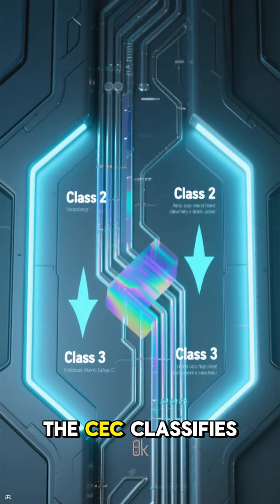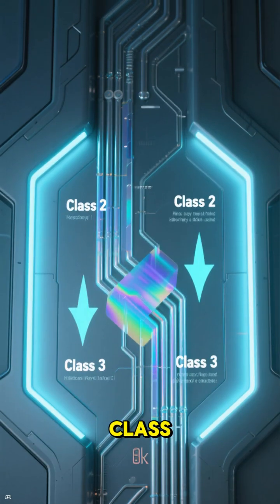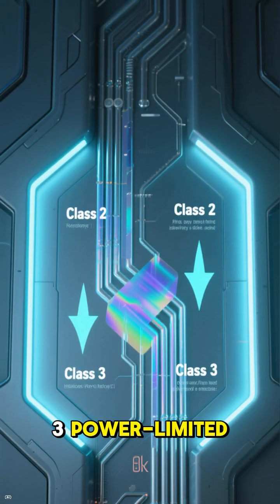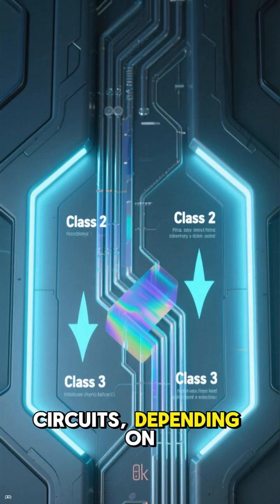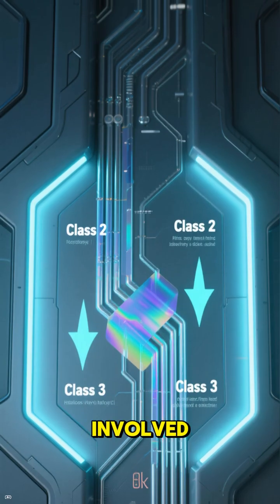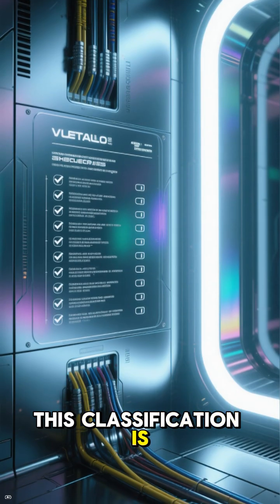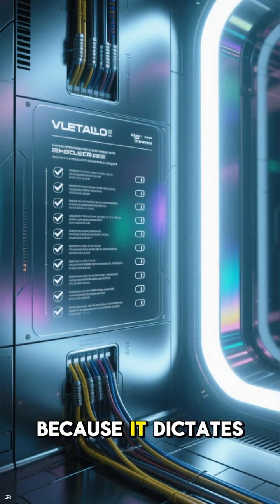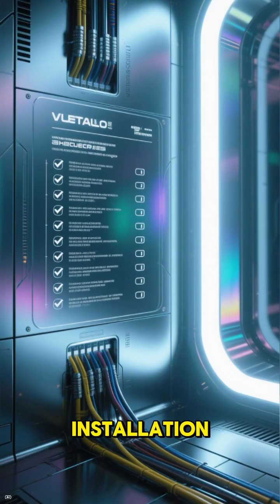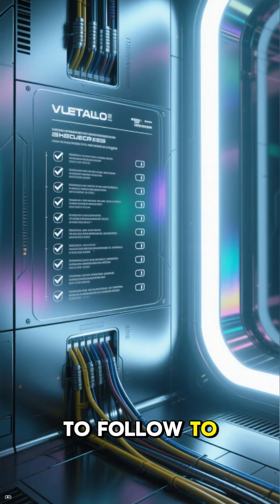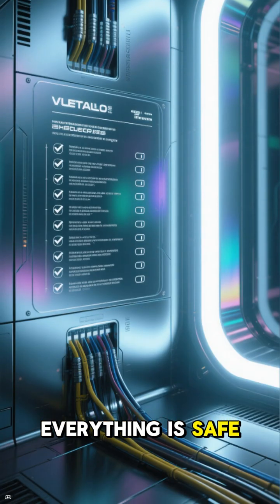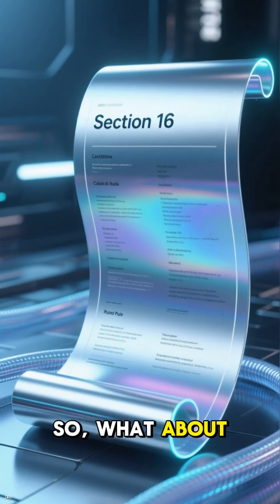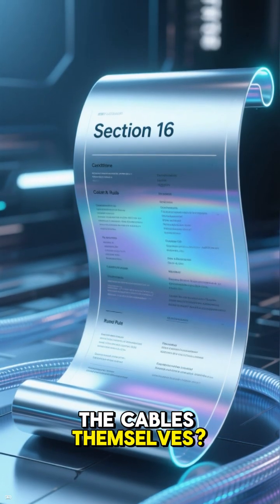The CEC classifies these systems as Class 2 or Class 3 power-limited circuits, depending on the power levels involved. This classification is super important because it dictates the wiring and installation rules we need to follow to ensure everything is safe.